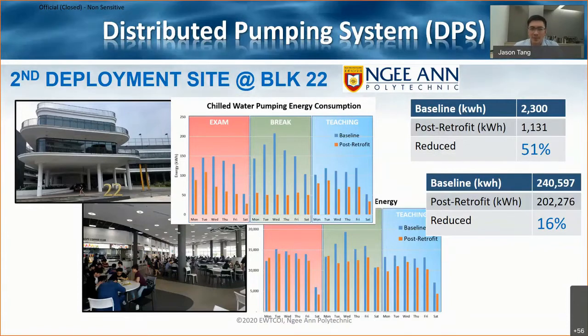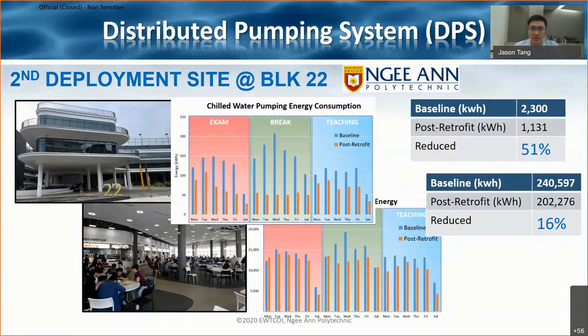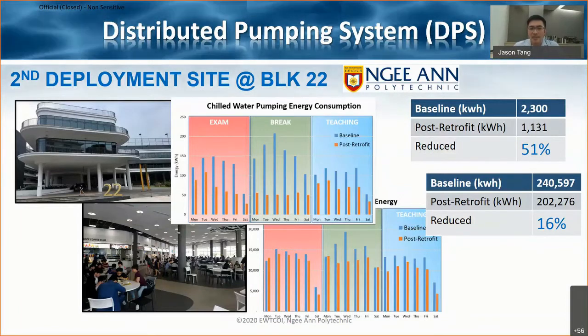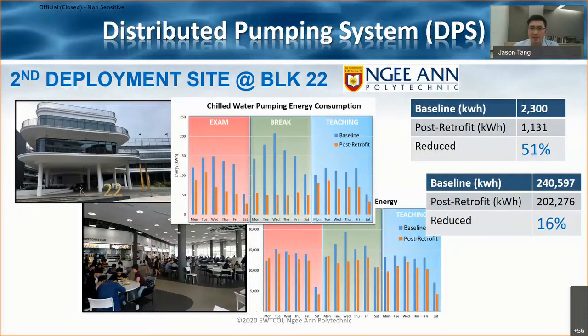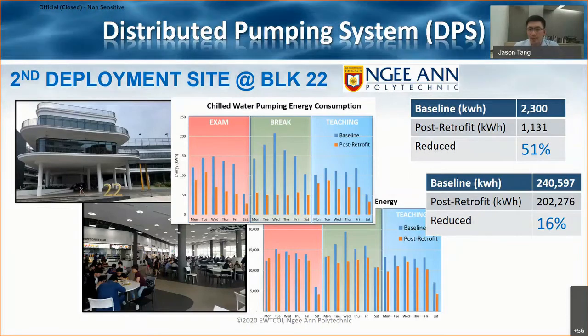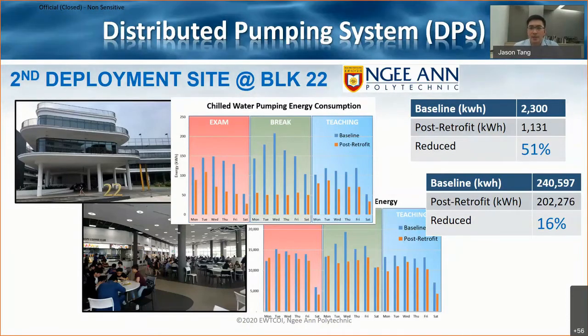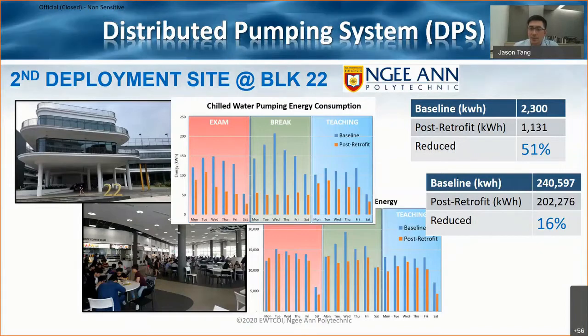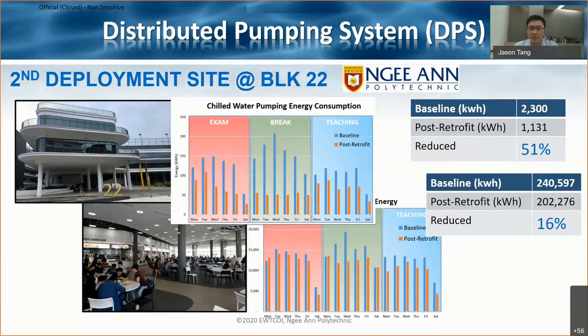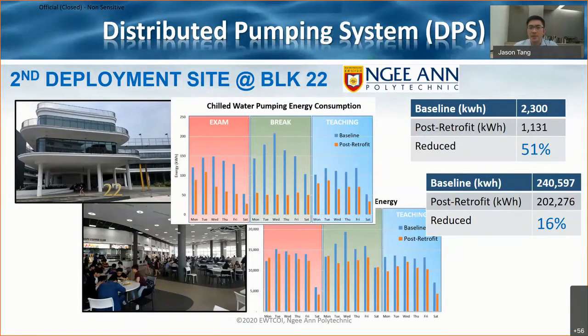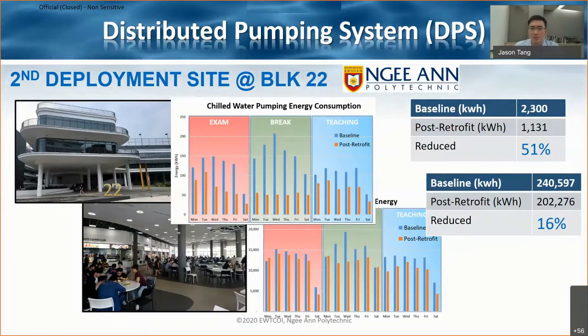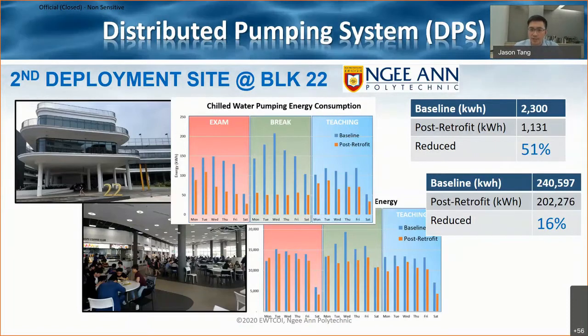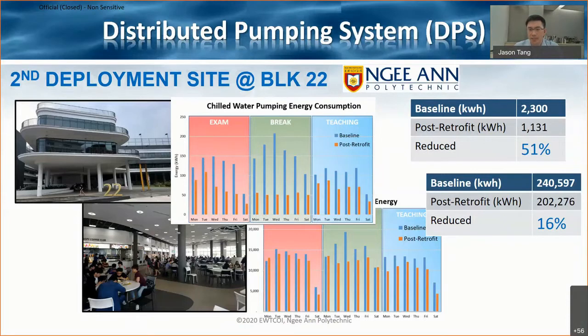Without evidence, no building owner would allow us to deploy this at their site, so we took a risk. We managed to convince our Ngee Ann estates team that this is a good system, and because we'd done the assessment ourselves, we were confident it would work. True enough, you can see the values on screen - our baseline showed we saved approximately 51%, close to the 55% and 50% calculated from the simulation studies. The same held for chiller savings - we had a 16% chiller saving.